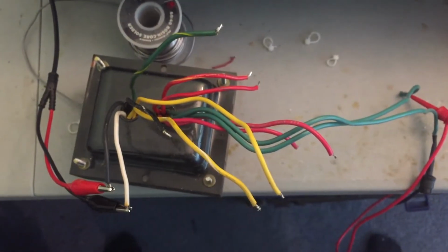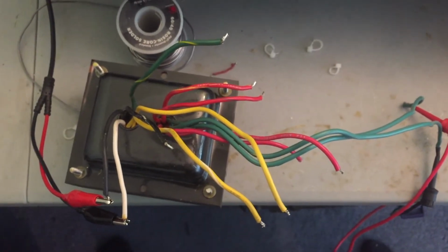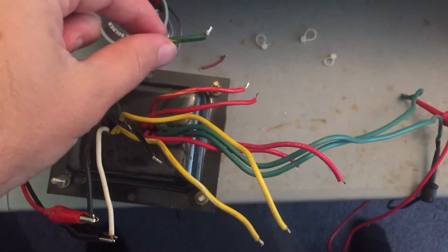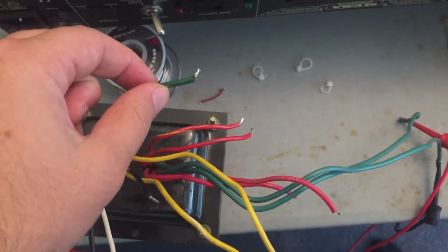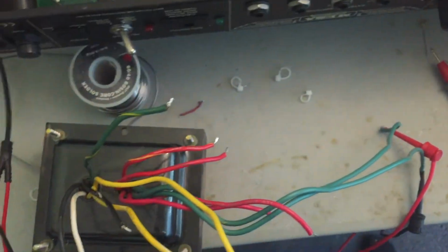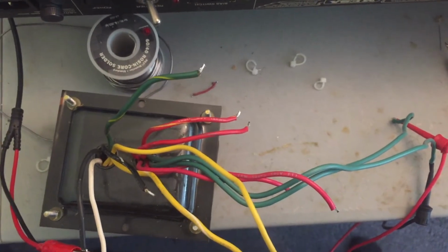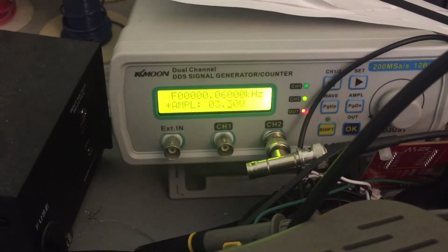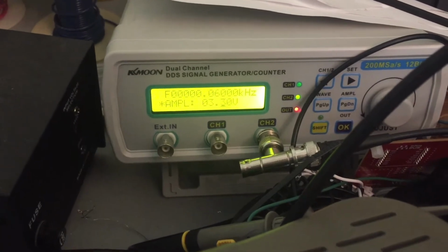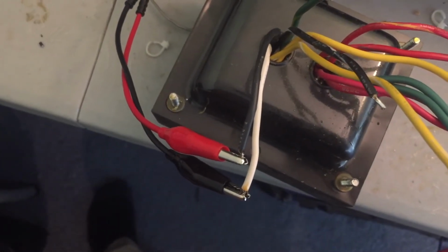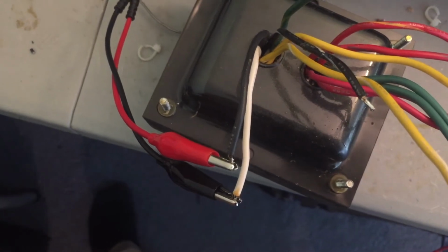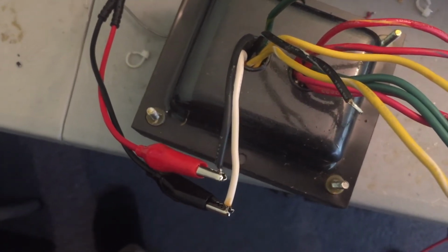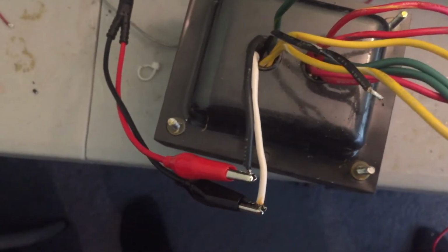After taking a closer look, it looks like the input transformer is actually doing what it's supposed to do, and they've just arranged it so the ground wire is attached to the center tap of the heater wires. To test this transformer, I have a function generator applying 60 hertz, 3.3 volts peak to peak to the input of the transformer, and that reads as 1.15 volts AC, or 1/100th of 115 volts AC. So I can go and read off all the voltages and verify that they're correct.